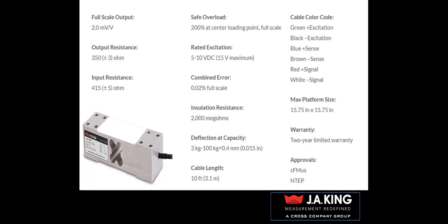Before starting a load cell test, make sure to have the specific load cell's spec sheet. The things you will need from the spec sheet are cable color code for proper wiring and testing purposes, full-scale output, the output resistance, and input resistance. These are for testing the resistance between the signal wires, which is the output, and excitation wires, which are the input.